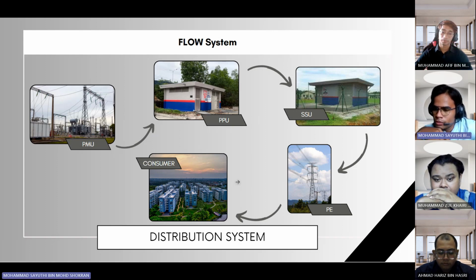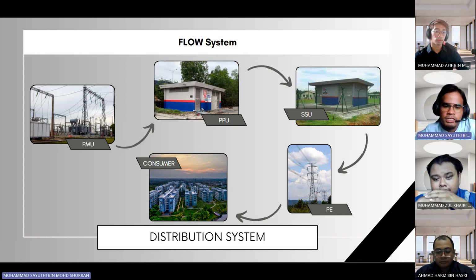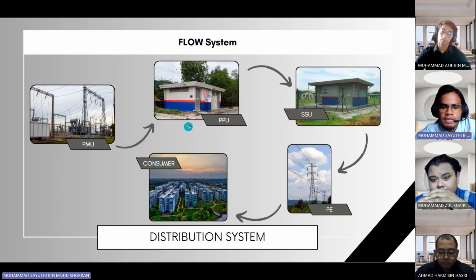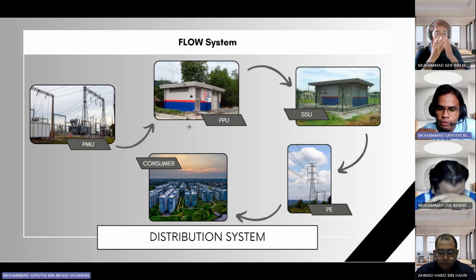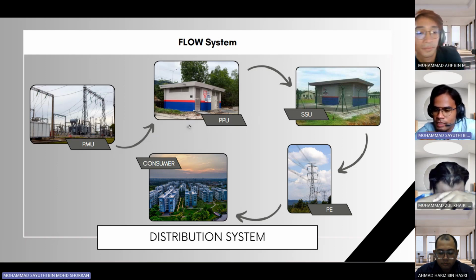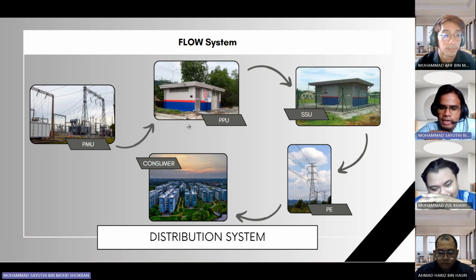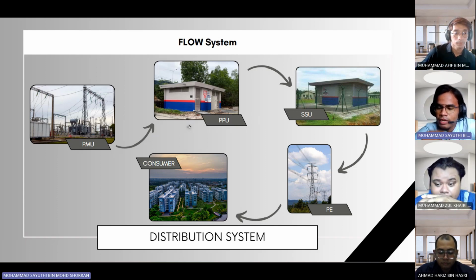Next we move to the PPU, main distribution substation, pencawang pengagihan utama. The PPU is used on the 33 kilovolt system to connect the 33 kilovolt network with the 11 kV network. It injects capacity into the 11 kV network through 33/11 kV transformations.